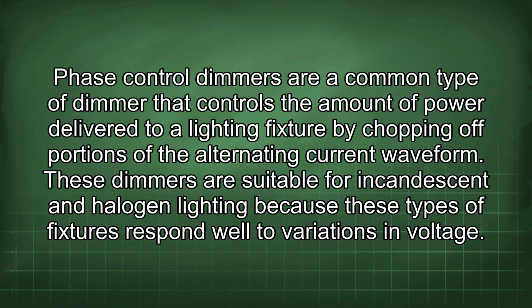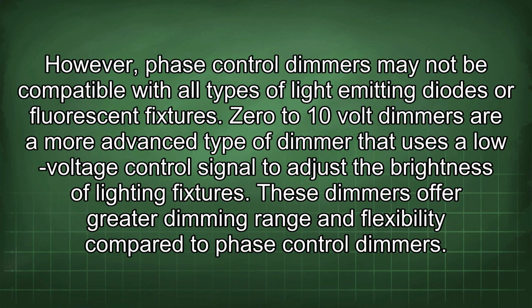Phase control dimmers are a common type of dimmer that controls the amount of power delivered to a lighting fixture by chopping off portions of the alternating current waveform. These dimmers are suitable for incandescent and halogen lighting because these types of fixtures respond well to variations in voltage. However, phase-control dimmers may not be compatible with all types of light-emitting diodes or fluorescent fixtures.